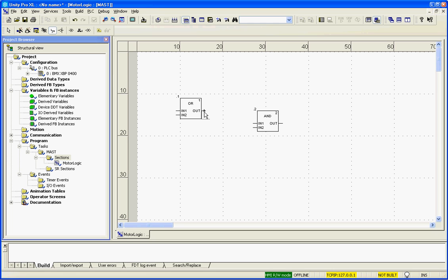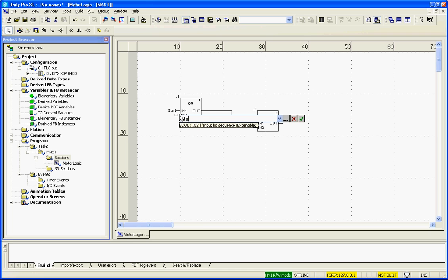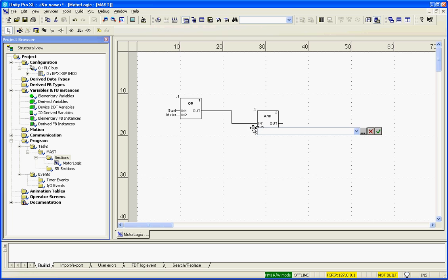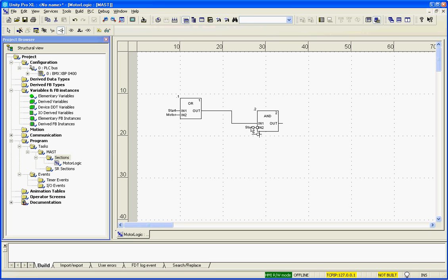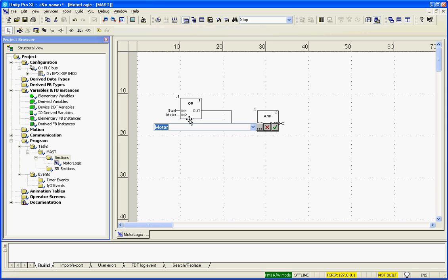I will link the OR with the AND. I'm going to put my start. This is my latch circuit. So this will be my motor. My stop. And because the stop is normally closed, I'm going to NOT it, which is the little NOT gate. And then my output is also going to be my motor.